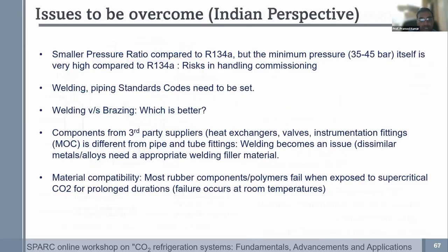Okay, so specific issues with India: one is, of course, that with carbon dioxide based systems the pressures are significantly higher. So you're operating at close to 100, 120 bar, and every rise in pressure above, say, 20 bar is actually quite risky. So you have to ensure that your systems are very well designed, and that your pipe standards and welding standards are maintained. I would recommend that you go for all stainless steel or copper construction with orbital weld systems.